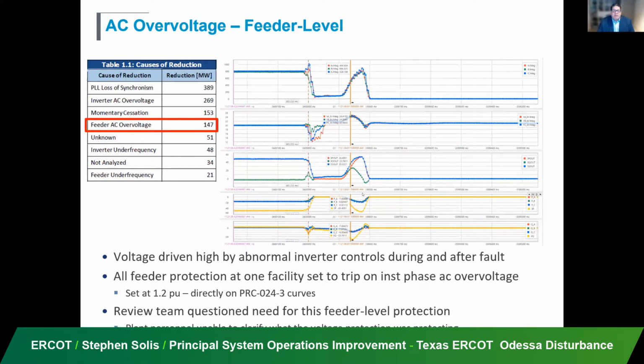One thing that was interesting here is that a lot of times units were coming on, and while their equipment, for example, may be able to handle up to 1.5 per unit, because the ride through requirement was at 1.2, they would set the relay settings right at 1.2 instead of utilizing their equipment capability. It was a misunderstanding of the particular rules. You really want to set it no lower than the requirements, but utilize your equipment capabilities so that you have more resilience in being able to ride through the disturbance.